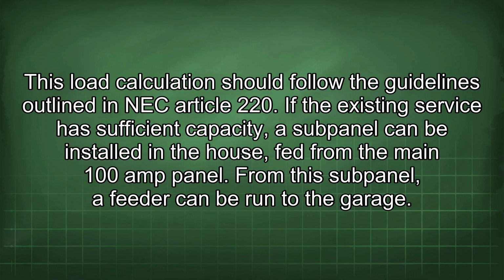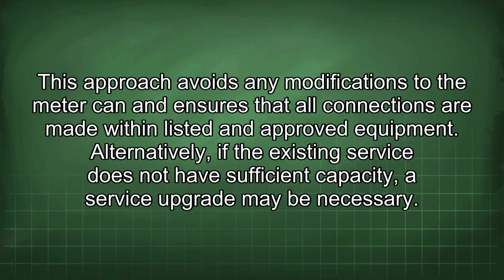If the existing service has sufficient capacity, a subpanel can be installed in the house, fed from the main 100 amp panel. From this subpanel, a feeder can be run to the garage. This approach avoids any modifications to the meter can and ensures that all connections are made within listed and approved equipment. Alternatively, if the existing service does not have sufficient capacity, a service upgrade may be necessary.